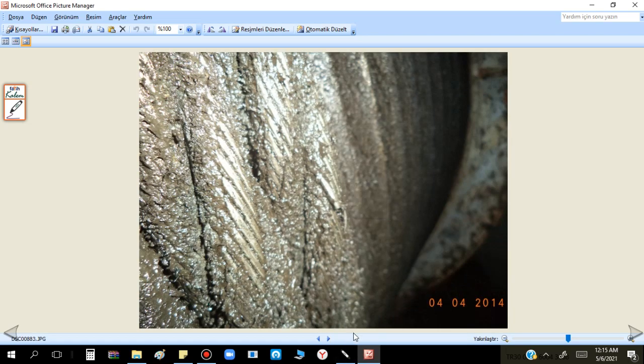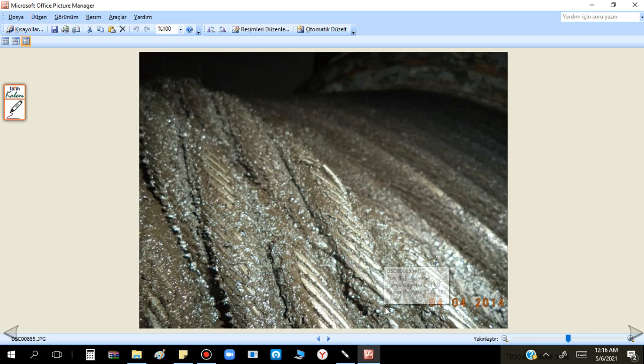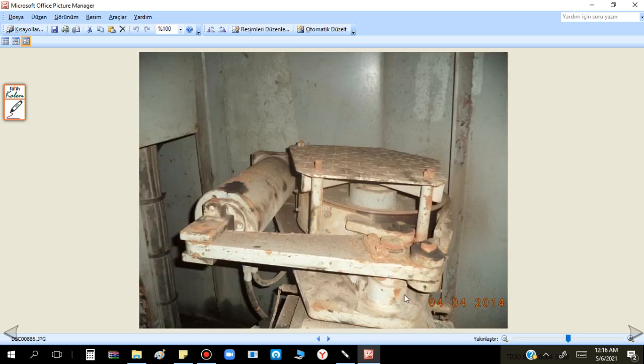You see small, small wires. In the McGregor video I have already talked about which strategy has to be followed about crane wire change. Everybody should have an idea about this - several broken wires you can see here.